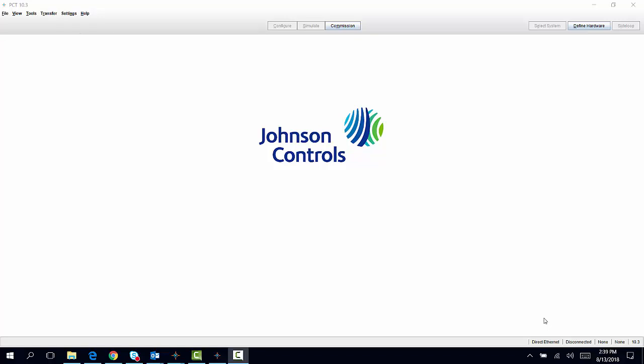To switch between the different controllers, simply go to Settings, Release Mode, and choose 10.3 for IP controllers and 10.2 for BACnet MSTP and N2 controllers at the current revision. For older controllers, simply choose the 10.0 release mode.